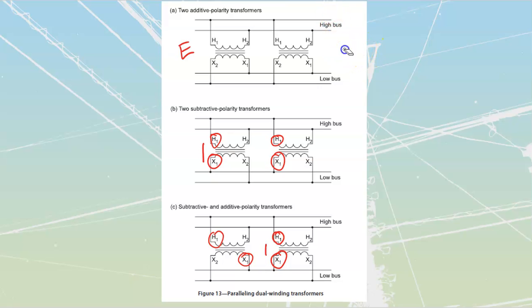So we want to be able to do these applications, paralleling up transformers, for a couple of reasons. Sometimes it's because we're adding onto a system. Other times it can simply be the pragmatic approach of - if I get myself a massive single transformer, that huge single transformer might not fit through the door of the electrical room.